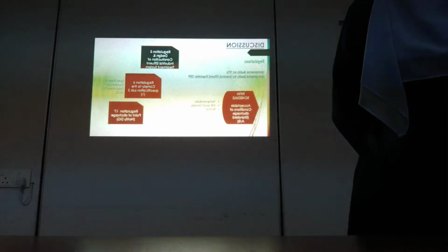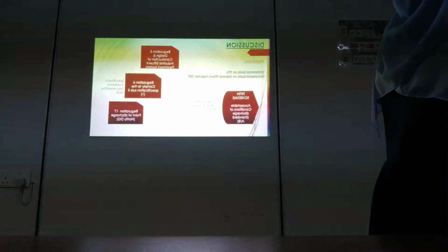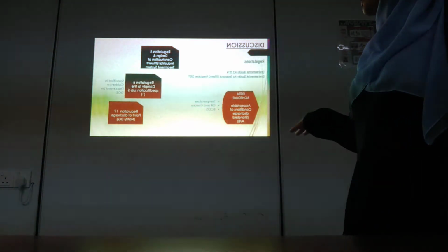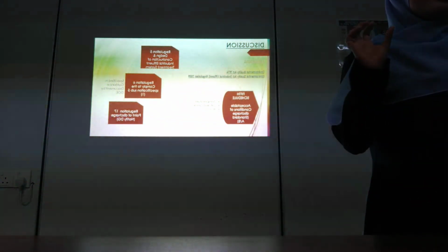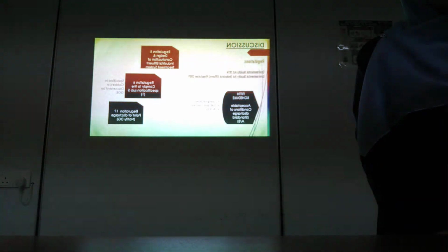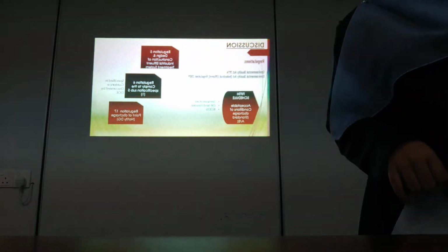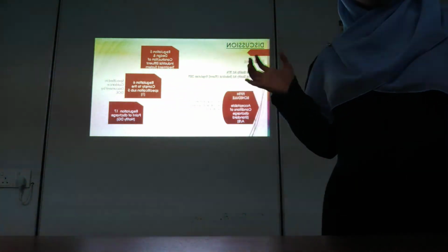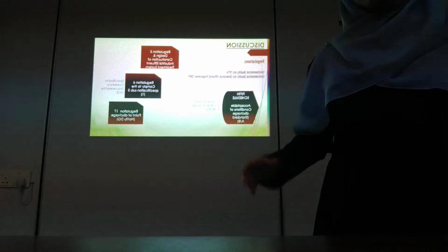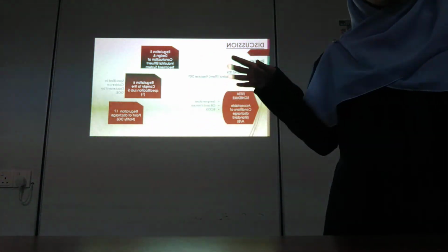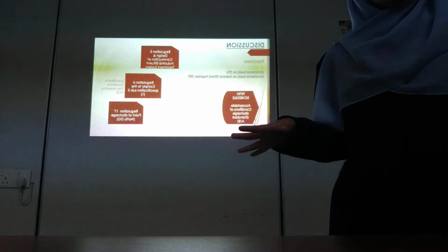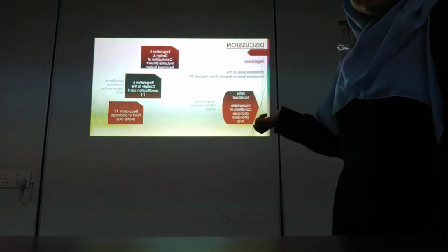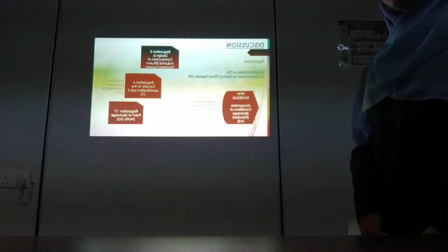First is regulation. Some of the regulations are under EQA 1974, with the sub-regulation EQIER 2009. It specifies, first, under the Fifth Schedule, the acceptable conditions of discharge, which should specify whether the effluent will be discharged to Standard A or Standard B, where A is upstream and B is downstream. Some of the conditions are temperature increase and also BOD 5 day.